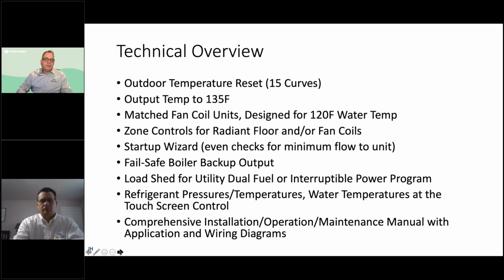If we're looking at using forced air heating or cooling, you want to match the system with an Enertech fan coil. Those fan coils are designed for 120 degree water temperature. So we don't need the boiler 160, 180 degree water temperatures for these fan coils. They're actually designed for the lower water temperatures we get from a heat pump.